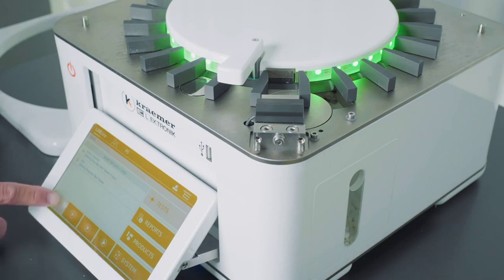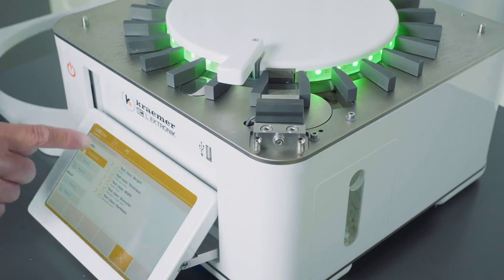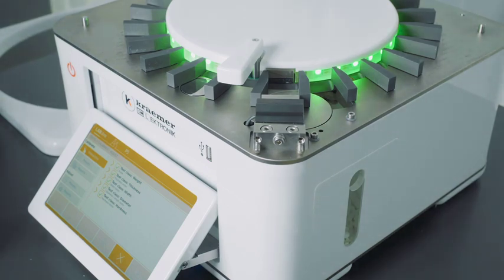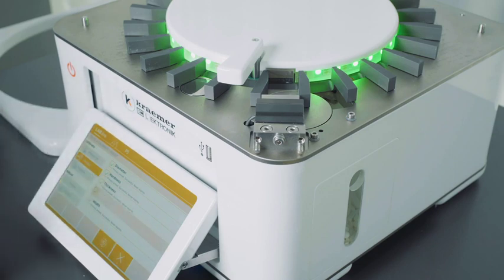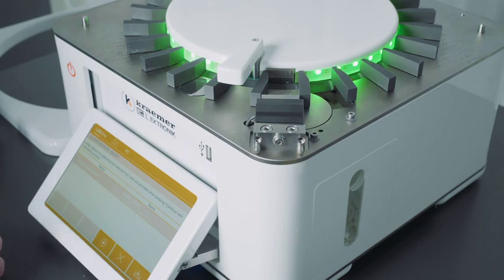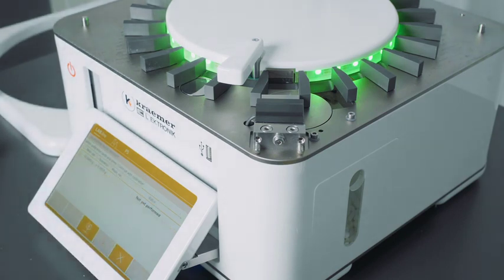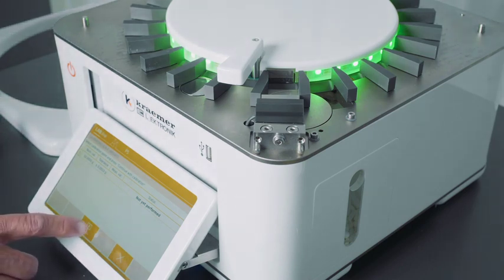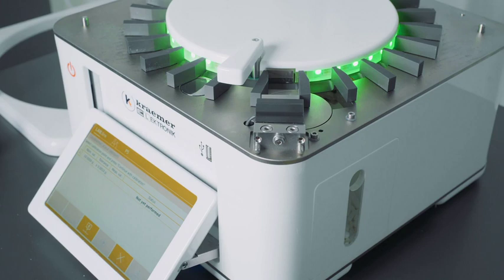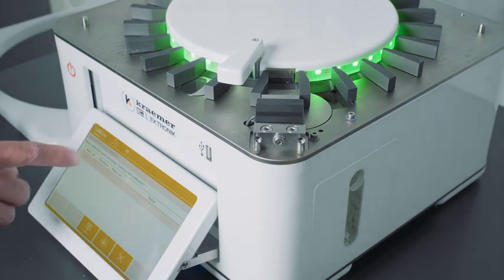For adjustment calibration, we can select here. You see a section calibrate, that is to verify the accuracy of the tester, and if the accuracy is not good, you can then go into adjustment mode. So we select here presets, and for example the weight, and press calibration, and we see we have here a 10 gram weight that is expected for the calibration.